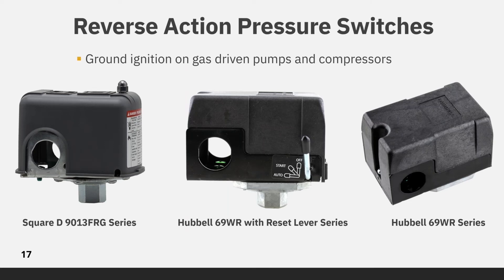Reverse action switches will cut in on rising air or water pressure. They are designed to ground ignition on gas driven pumps and compressors when a desired maximum pressure is reached. They can also act as a low pressure alarm or to prevent pump operation at low pressure. The reset lever is optional.